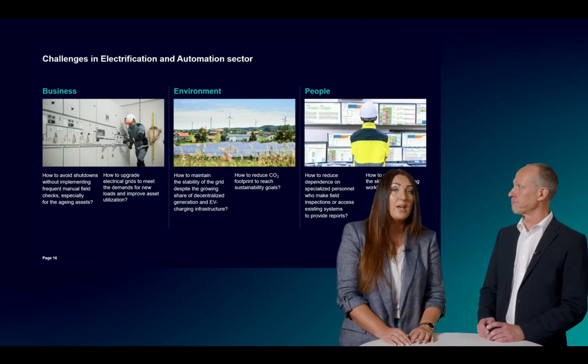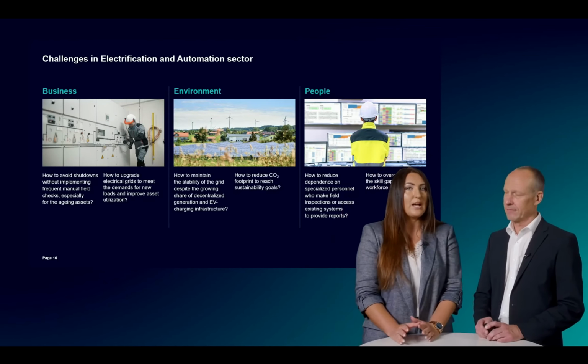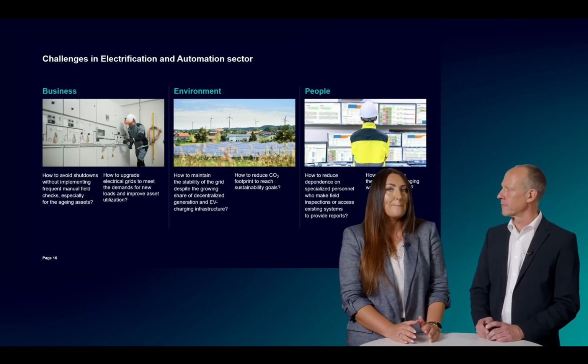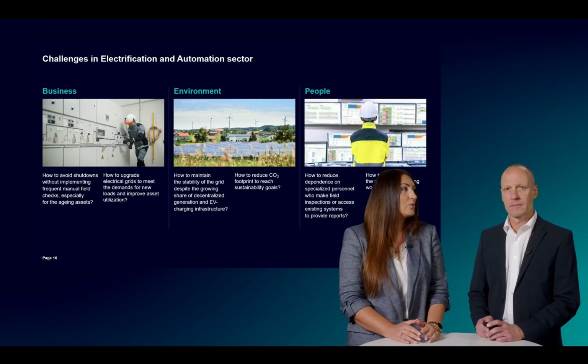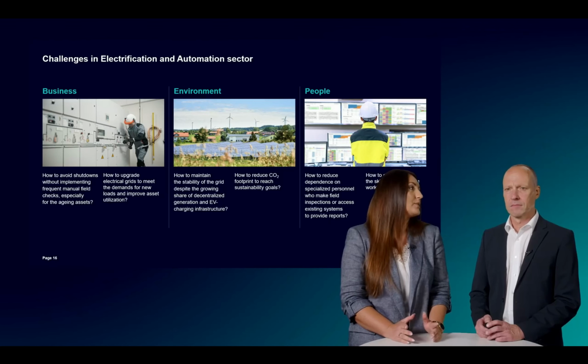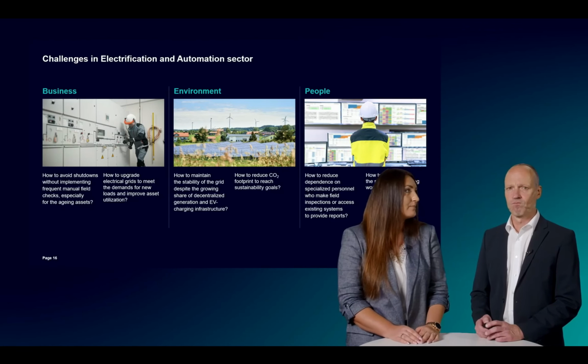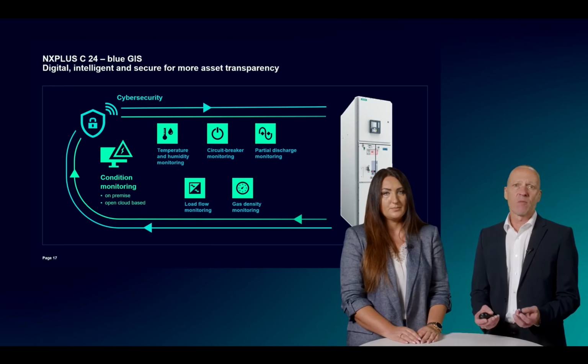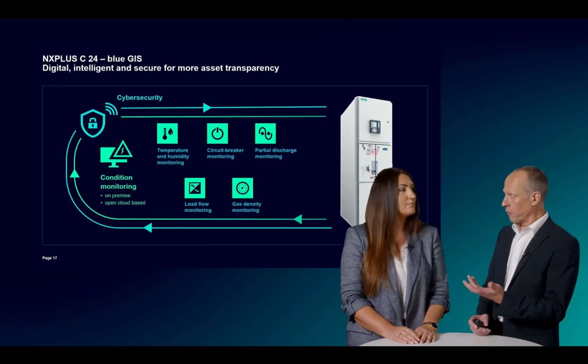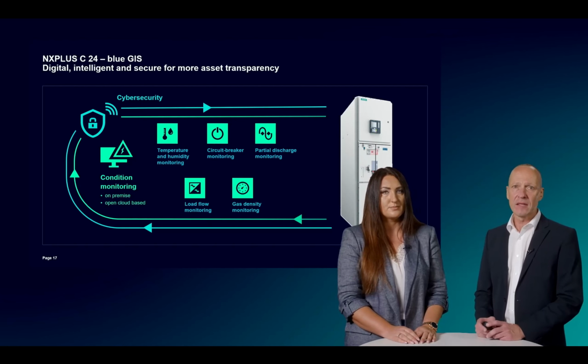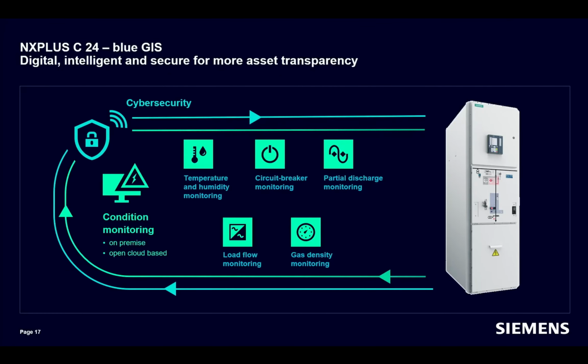So, sounds reasonable. But you mentioned now several times condition monitoring. Could you tell us a little bit more about what kind of monitoring Siemens is now already offering? Yeah, sure. Let's take one of our primary Blue GIS, what you have already shown before, the NX Plus C24 Blue GIS as an example. We have integrated sensors for temperature and humidity monitoring to detect abnormal operating and ambient conditions. The circuit breaker can be monitored to prevent switching failures.